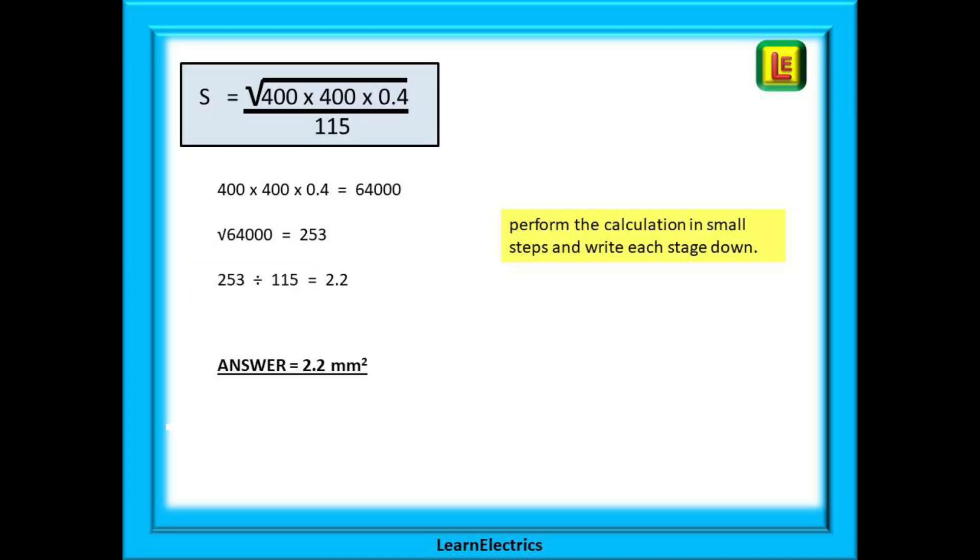It is now just a matter of putting these numbers into the formula and pressing the buttons on our calculator. Here are the numbers inserted into the formula. I find it best to split the calculation into several easy steps rather than to attempt to do it all in one go. So 400 times 400 times 0.4 gives us 64000 and the square root of 64000 is 253 rounded up. And 253 divided by 115 gives us an answer of 2.2 millimeters as a minimum size.